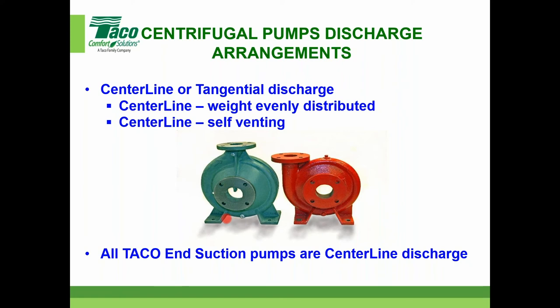What we mean by that is any air that gets in here, because invariably air gets into the piping system, especially during startup, right? Until everything's operational. So any air that gets in the pump, and centrifugal HVAC hydronic pumps don't like air inside of them, that's for sure. The pump doesn't remove it from the system, but it does find its way out, right? Because it goes out the highest point. This here could get trapped a little bit right there. I think these folks that designed the tangential ones did that because for many, many moons, it was a higher efficiency pump, a couple of points higher efficiency.